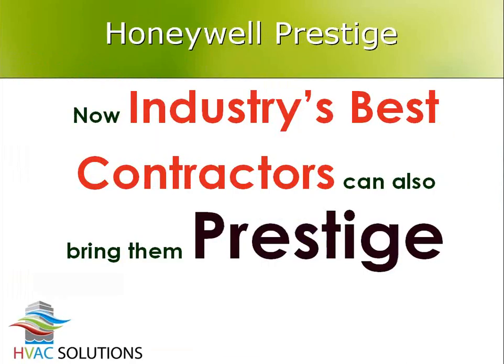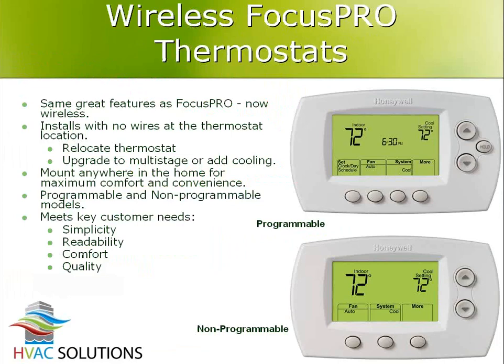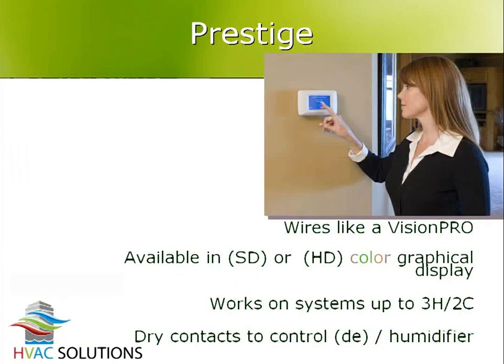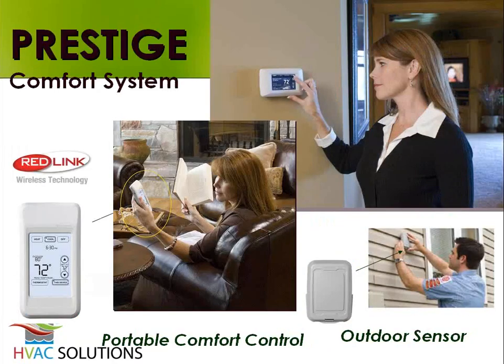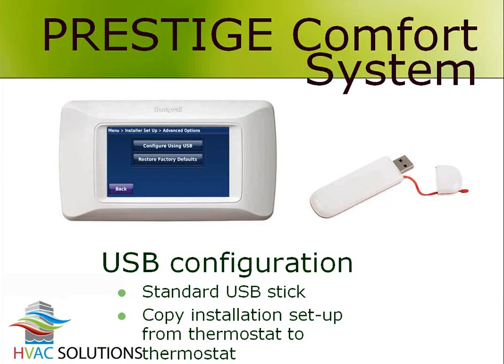Right? So let me jump back a couple screens for 1 second. The 2 FocusPRO stats are wireless everything. There's no wires on these stats at all. They get batteries put in them. They talk wirelessly down to the equipment control module by the furnace, and that's it. No wires at the stat. The Prestige is a little bit different. The Prestige requires wires to the furnace. However, the accessories are what the wireless part is.